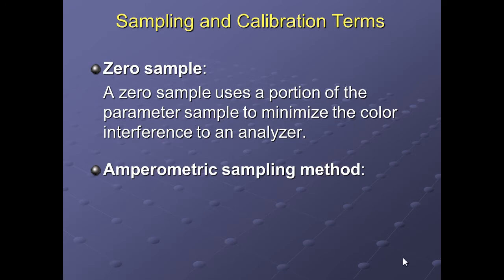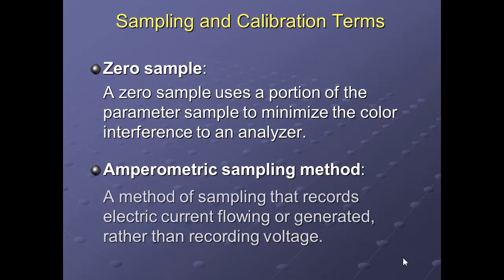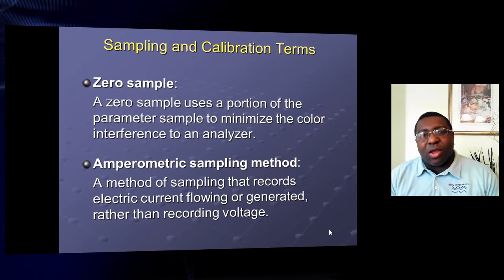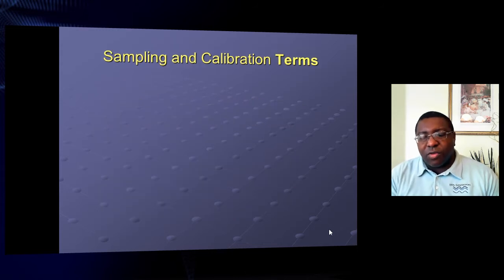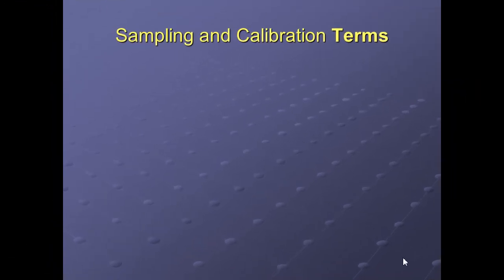Amperometric sampling methods use electric currents flowing to generate readings rather than recording voltage — so you're using electrical current, either hand-cranked or plugged in, and recording a milliamp reading from the meter.